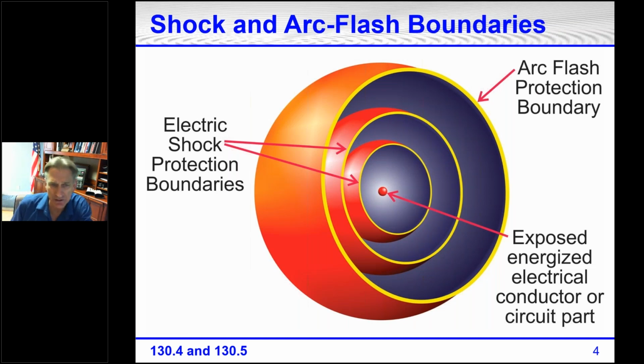One of the things to notice about this drawing that I did is that I have the arc flash boundary the furthest out from the 2 shock boundaries. That's not always the case. Arc flash boundary and shock boundaries are not dependent on each other. One doesn't have anything to do with the other.